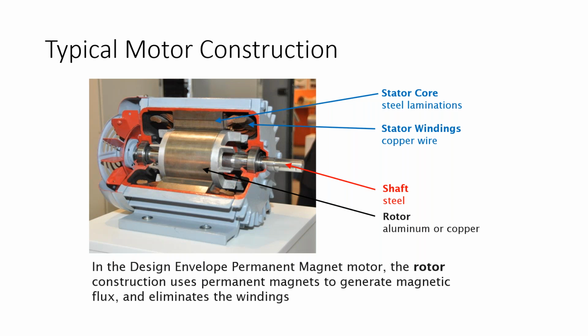So generally we're looking at a cutaway of a motor here, and all of you that took electrical engineering for mechanical engineers, or you might have taken a motor class, the stator core has steel laminations and windings, right? And the copper side, you'll have a steel shaft and a rotor. In a permanent magnet motor, the motor construction uses magnets to generate a magnetic flux, and we eliminate the windings. These magnets are substantially lighter weight than the copper windings that are necessary in a four-pole design. So right there, you'll see the rotor of aluminum and copper, and that whole section is now magnetic.